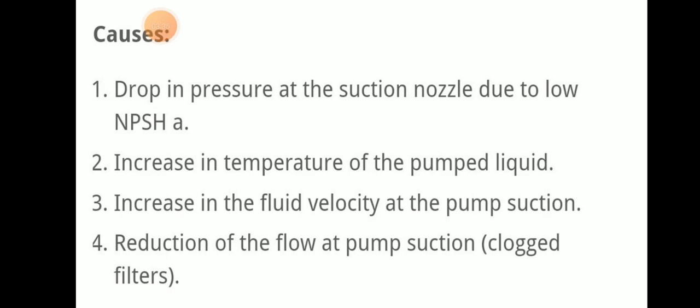So what are the causes of cavitation? Drop in pressure at the suction nozzle due to low net positive suction head, increase in temperature of the pumped liquid, increase in fluid velocity at pump suction, reduction of flow at pump suction, or clogged filters. These are the causes of pump cavitation.